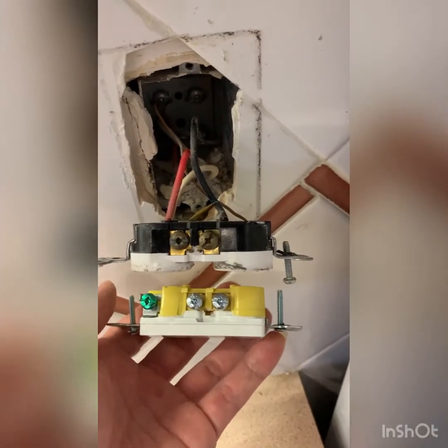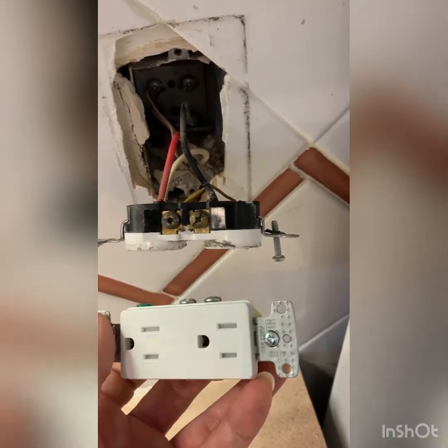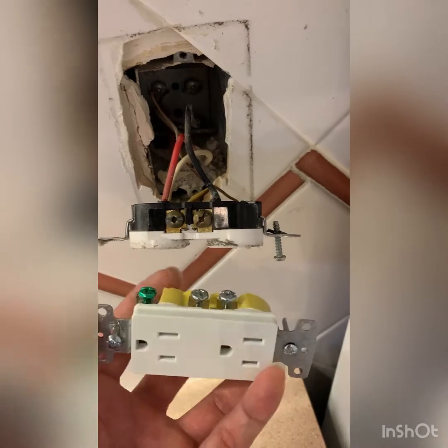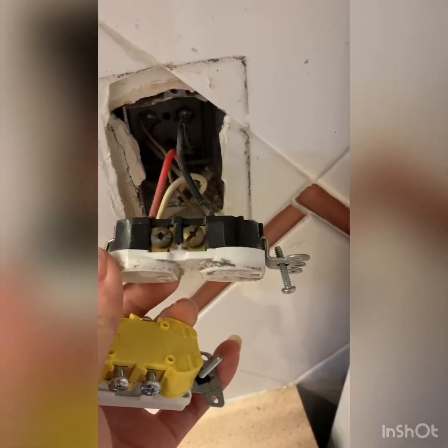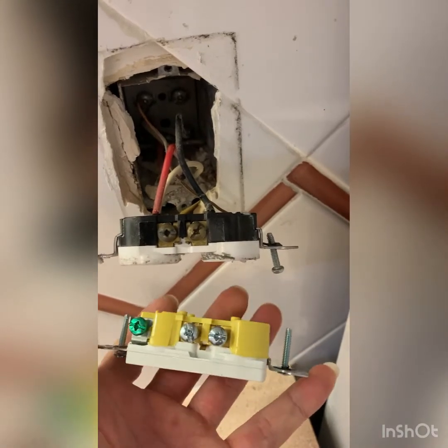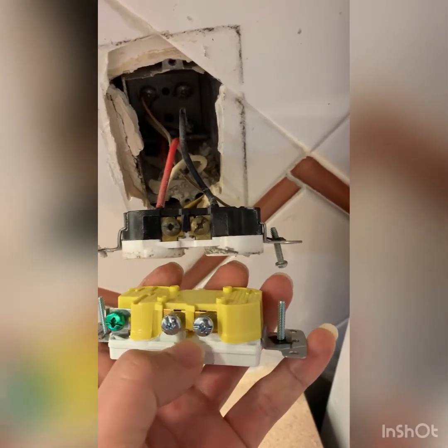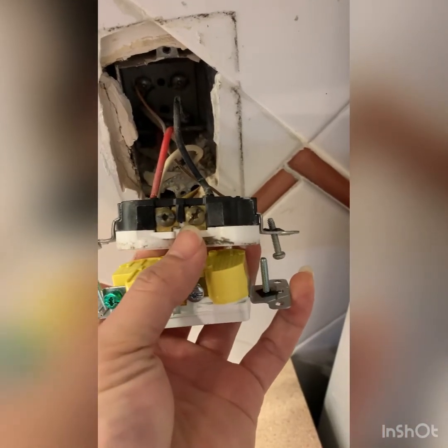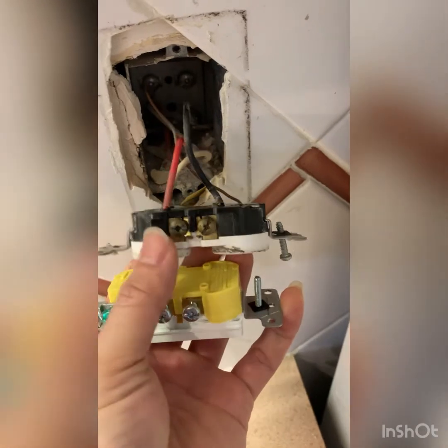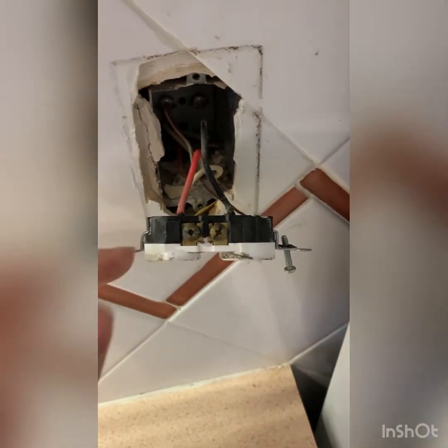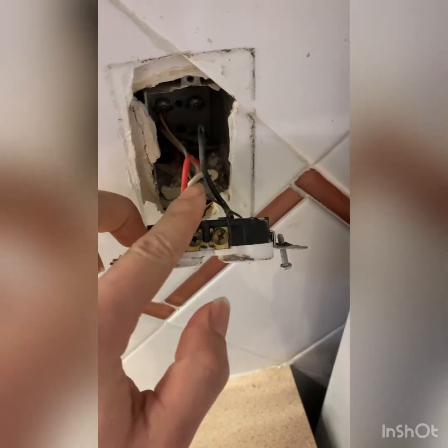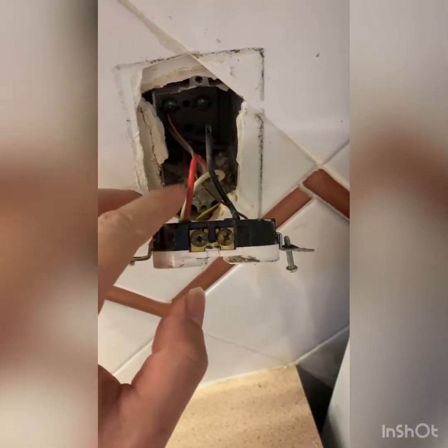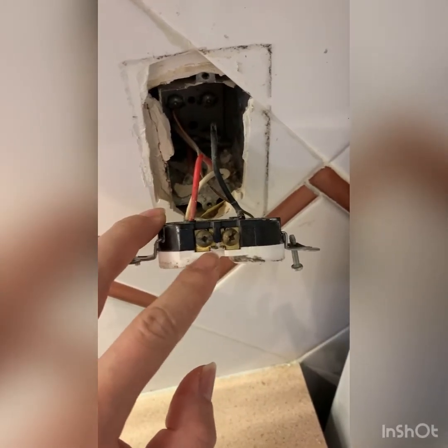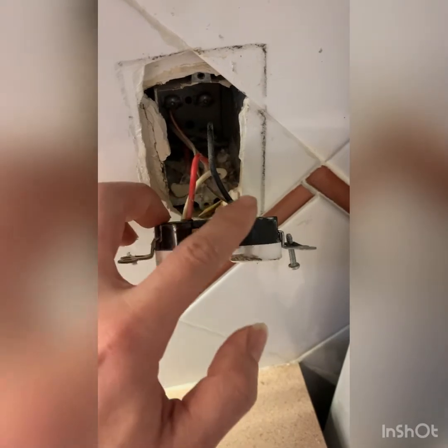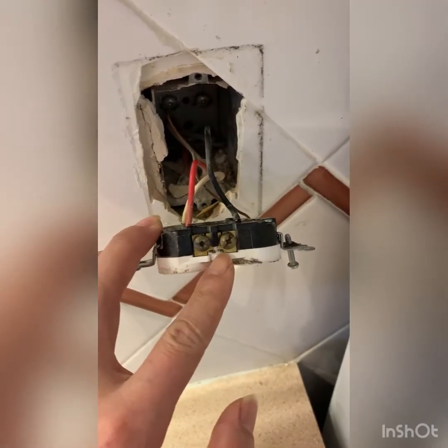As you can see, this is the brand new, updated, tamper resistant receptacle. This is the split receptacle. It's called a split receptacle because they take this bridge off and snap it off. As you can see here, they snap it off. Why do they do that? Because they want to connect the black and red wires to these two terminals, providing two independent circuits. They share this neutral here.